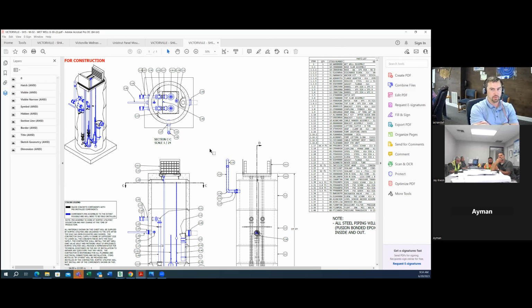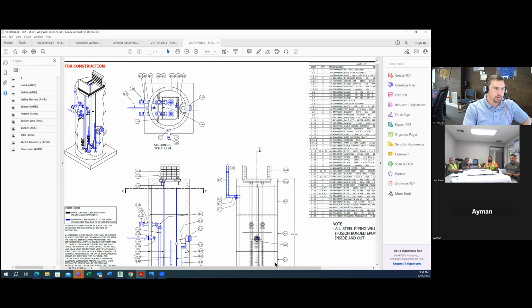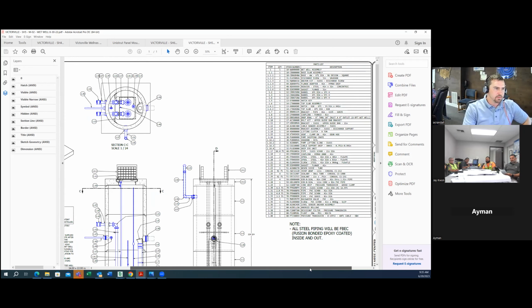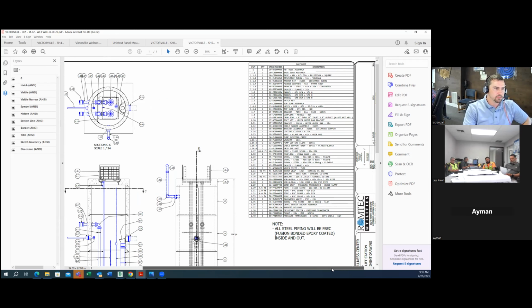Yeah, but anyone we've done, we typically just pull cable to it. I typically don't see the electrician being responsible for lowering the pumps. Yeah, I'll typically get our sheets on that to the installing contractor. So those are 5 horsepower, right? So about 150, 200 pounds, something like that. But anyway, it's a right console scope. You lower it down. And I give you a mechanical installation recommendation and the plumbing recommendations. I give you the electrical recommendations to you.